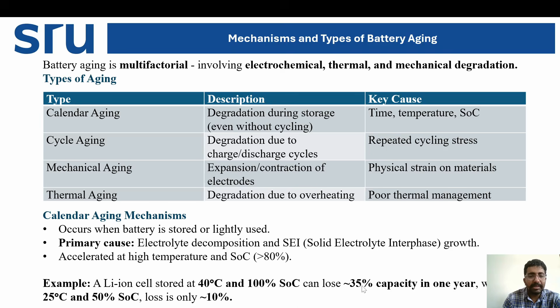Now we move to cyclic aging. In cyclic aging, the charging and discharging cycle impacts the battery, causing it to lose efficiency. This degradation happens due to SEI growth, that is layer formation — electrolyte reduction forms a passivation layer, which creates problems, consumes lithium ions, and causes capacity fade. Then there's lithium plating.